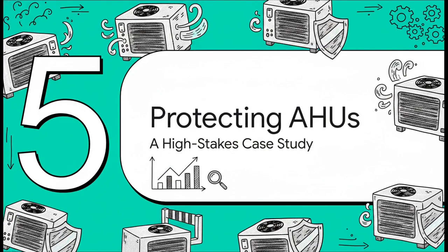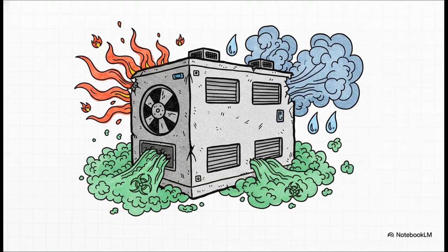So, how does all this theory actually play out in the field? Let's bring it all together in Section 5, Protecting Air Handling Units, with a real-world case study. Picture this: the extract air coming out of an indoor swimming pool. It is, without a doubt, the absolute perfect storm for corrosion. Your air handling unit is sucking in air that's sitting somewhere between 28 and 32 degrees Celsius, loaded with 50 to 60% relative humidity. But here is the real kicker. That air is packed with chloramines, specifically this incredibly aggressive nitrogen trichloride.